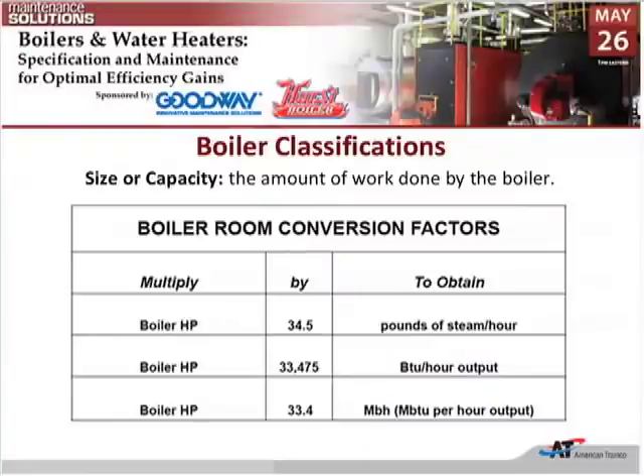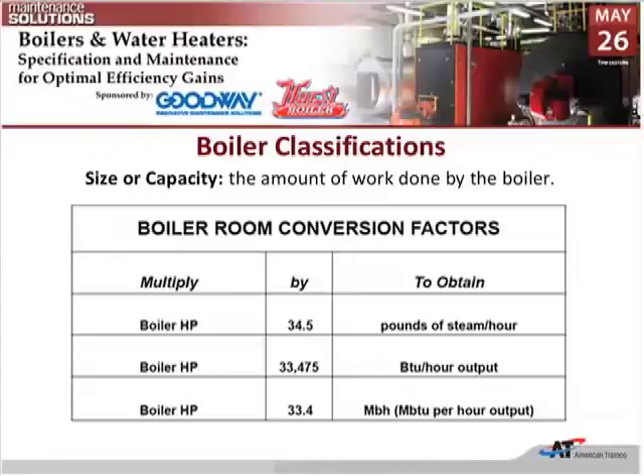That being the case, for me to get that amount of heat out in BTUs per hour, that means I'm going to have to purchase a lot more heat that I'm going to lose and give up. Our objective is going to be to find ways to prevent that from happening. A boiler horsepower can also be rated at approximately 42,000 BTUs an hour input, and if we look at how many millions of BTUs per hour we're purchasing, it comes out to about 33.4.